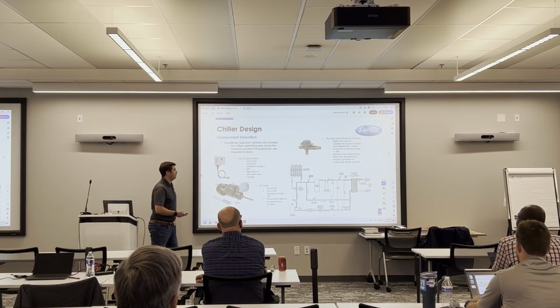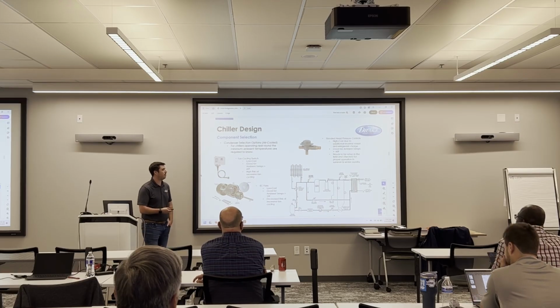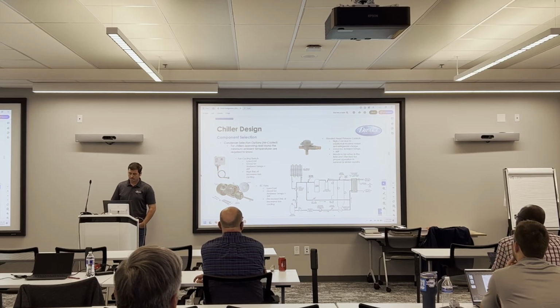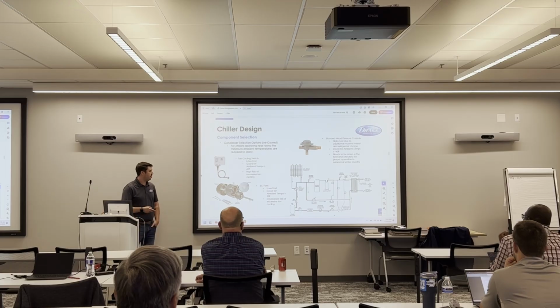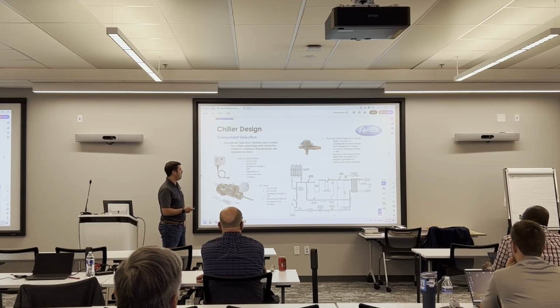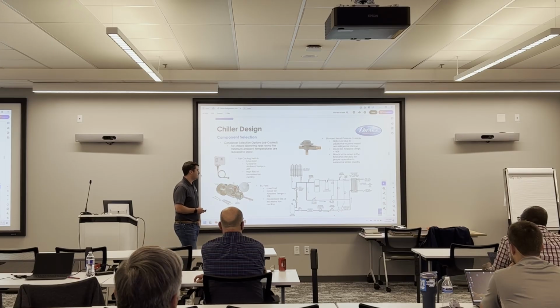Some other things with the head pressure controls: they need to be set up in the field generally and checked for proper operation in the summer and the winter time. Down below is just an example of a flooded head pressure valve I had put into a refrigeration system. So we can kind of talk about how this works.